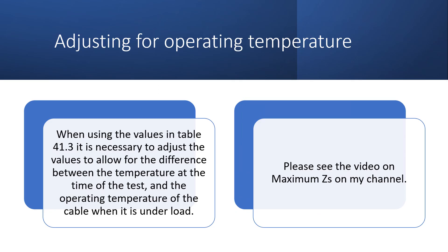The formula in appendix 3 shows that ZS max must be less than or equal to 0.8 multiplied by UO multiplied by C min, divided by IA. This basically multiplies the value from table 41.3 by 0.8, which reduces the value by 20% to allow for the difference in operating temperature. I explain this further in another video on my channel regarding maximum ZS, and I'll put a link at the top of the screen.